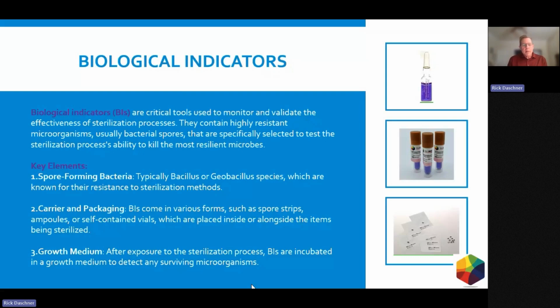So key elements: spore-forming bacteria, typically Bacillus or Geobacillus species, which are known for their resistance to sterilization methods. Packaging: biological indicators come in various forms, such as spore strips, ampules, and self-contained vials, which are placed inside or alongside the items being sterilized. Off to the side there, you can see we've got an ampule, we've got a self-contained biological indicator, and then the picture on the right shows some steel discs that we would inoculate with spores. And then the growth medium: after exposure to the sterilization process, biological indicators are incubated in a growth medium to detect any surviving microorganisms. In some cases, like a self-contained biological indicator, the growth medium is already in it, whereas with others you would add it upon incubation.